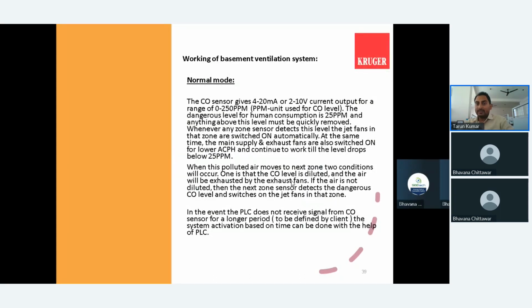Now the working principle of the basement ventilation system. One is the normal mode and the other is the fire mode. Basically this will be decided by the CO sensor. Anything above 25 ppm is not okay for the human body. So there will be a CO sensor which will detect the CO level in the basement. It will give the signal to the panel, and on that basis the panel will start running the fans at low speed and high speed, because a jet fan always comes with two speeds: one is low speed and the other is high speed.